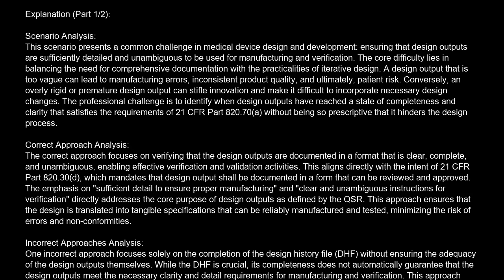Correct approach analysis. The correct approach focuses on verifying that the design outputs are documented in a format that is clear, complete, and unambiguous, enabling effective verification and validation activities. This aligns directly with the intent of 21 CFR Part 820.30(d), which mandates that design output shall be documented in a form that can be reviewed and approved.